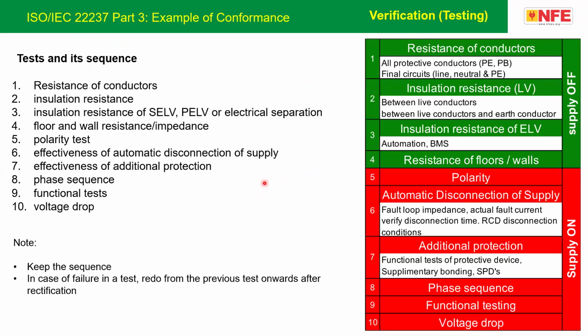Similarly, multiple subjects are to be tested, starting with the continuity resistance of conductors, insulation resistance, floor and wall resistance, impedance test, polarity test, effectiveness of automatic disconnection of supply, effectiveness of additional protection, and so on. So basically, there is a sequence of design requirement, selection, erection requirement, and verification in the form of inspection and testing. These are actually mandatory as per ISO IEC 22237.